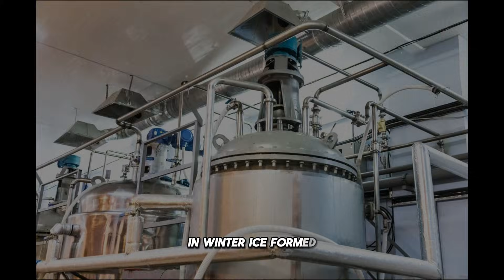The problem was that the river did not cooperate. In winter, ice formed, flow dropped, water temperatures approached freezing. And exactly at the same time, the city's demand for heat peaked. In summer, snowmelt flooded the system. Water temperatures rose. Sediment loads shifted. The river was alive, seasonal, unpredictable. A cooling system designed for a stable river could not survive here. So engineers built an intake system that treated river water as hostile until proven otherwise. Screens removed ice and debris before they could choke flow. Settling tanks stripped out silt. Everything happened underground, protected from the same environment it was fighting.